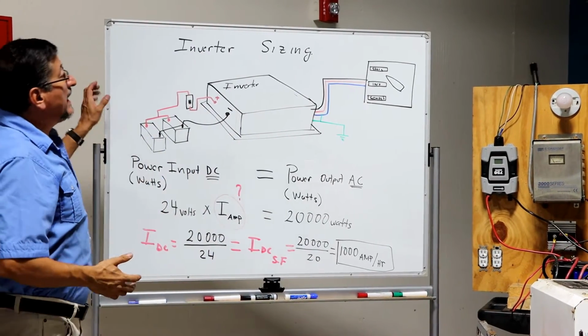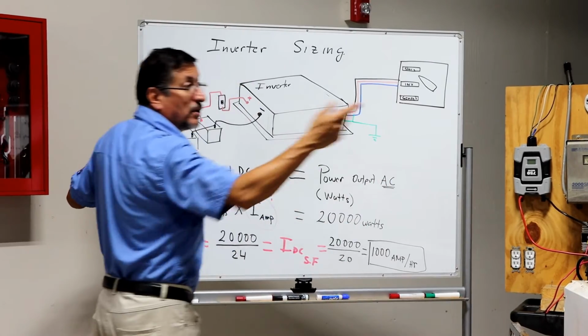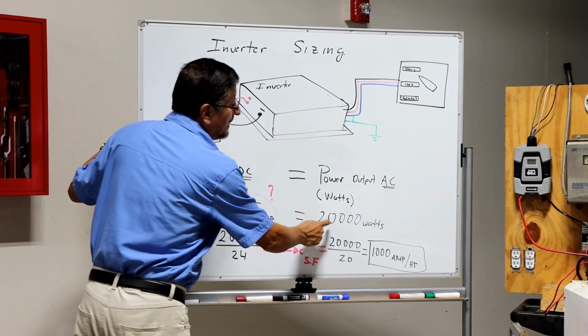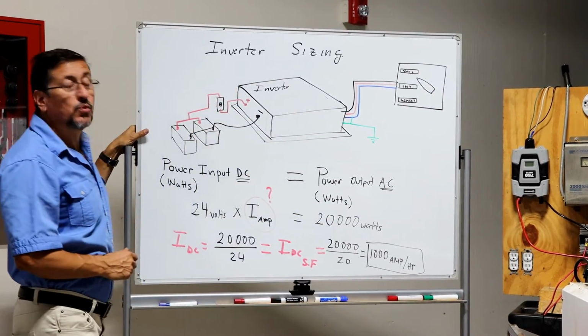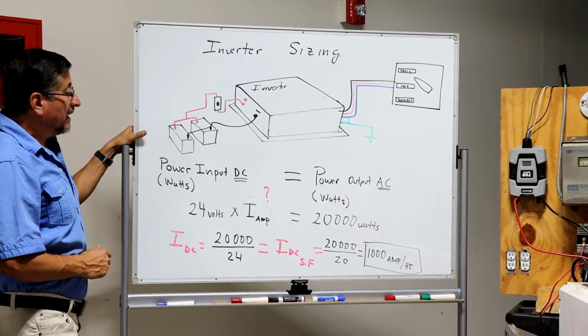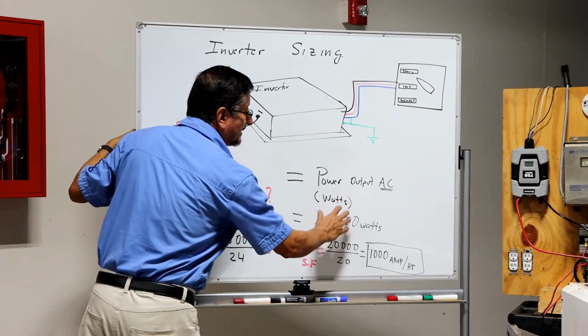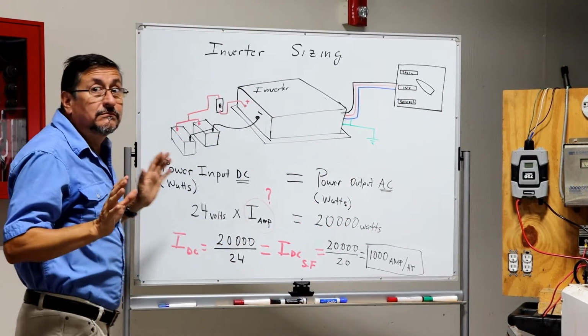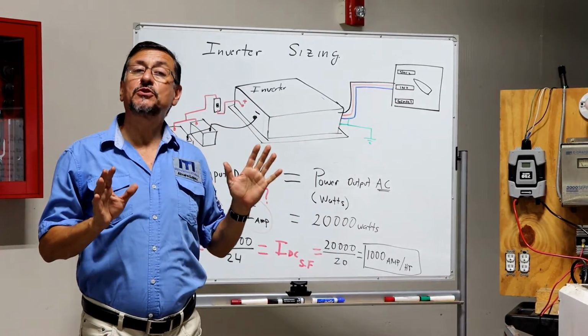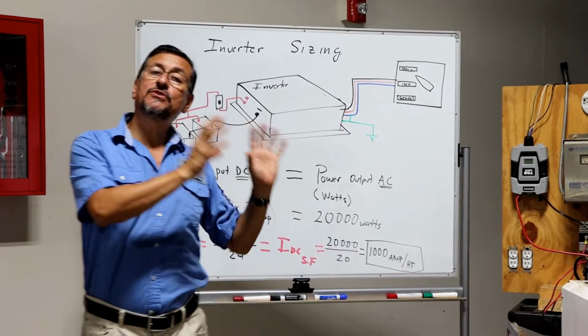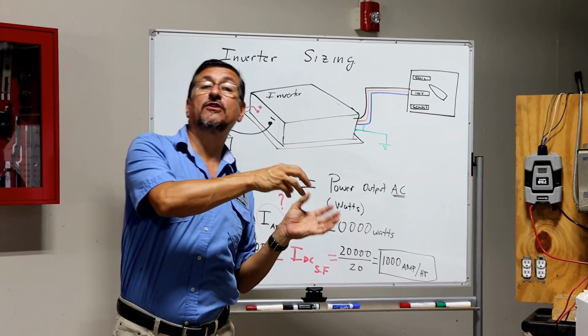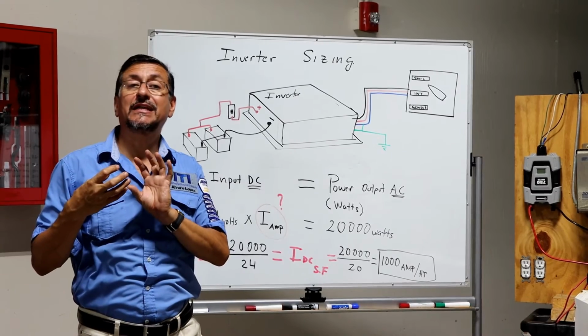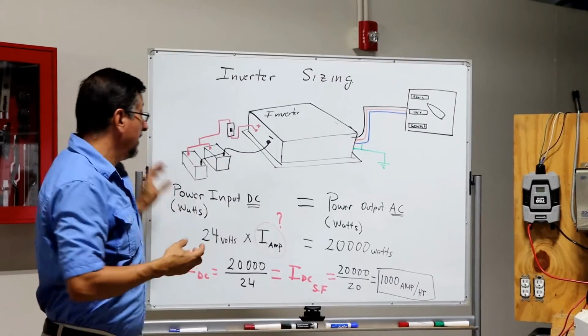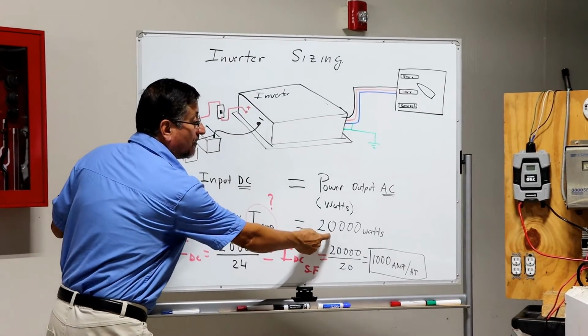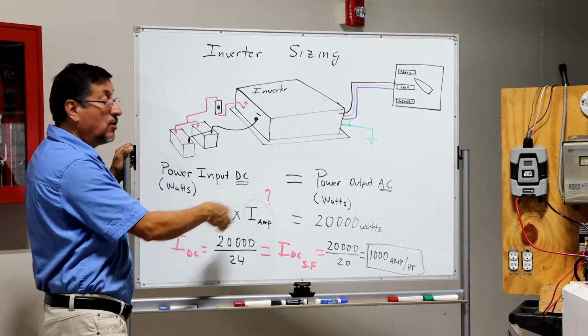All right, I need, according with our example, 20,000 watts. I need 20 kilowatts. This is the power that I need in the AC side. The power should be the same. The power produced in AC is coming from the power entering in the DC side. If I need 20 kilowatts over there, it's because I have 20 kilowatts.